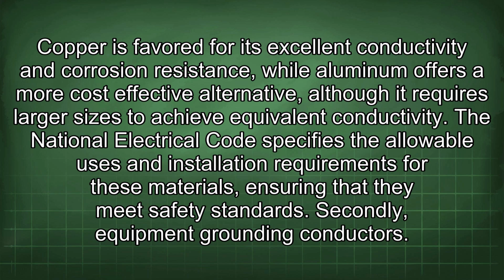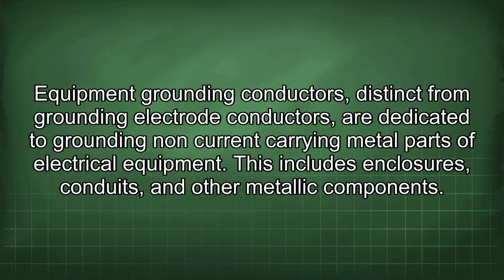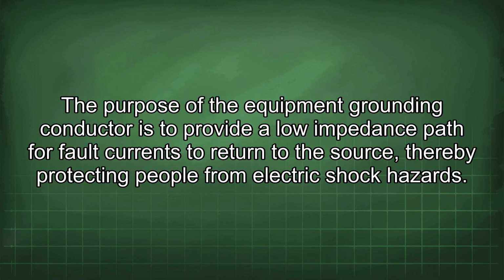Secondly, equipment grounding conductors. Equipment grounding conductors, distinct from grounding electrode conductors, are dedicated to grounding non-current carrying metal parts of electrical equipment. This includes enclosures, conduits, and other metallic components. The purpose of the equipment grounding conductor is to provide a low impedance path for fault currents to return to the source, thereby protecting people from electric shock hazards.